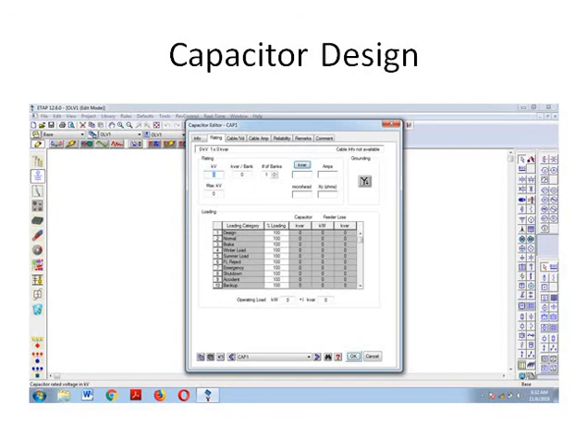Improving the power factor by implementation of the capacitor bank is definitely one aspect, but the other aspect is increasing the capacity of the line. That is one more aspect. Further, there may be certain violations which may happen, and it's never advisable to directly install the capacitor bank without having any previous studies. So these electrical software tools give an opportunity for power system engineers to try and explore things.